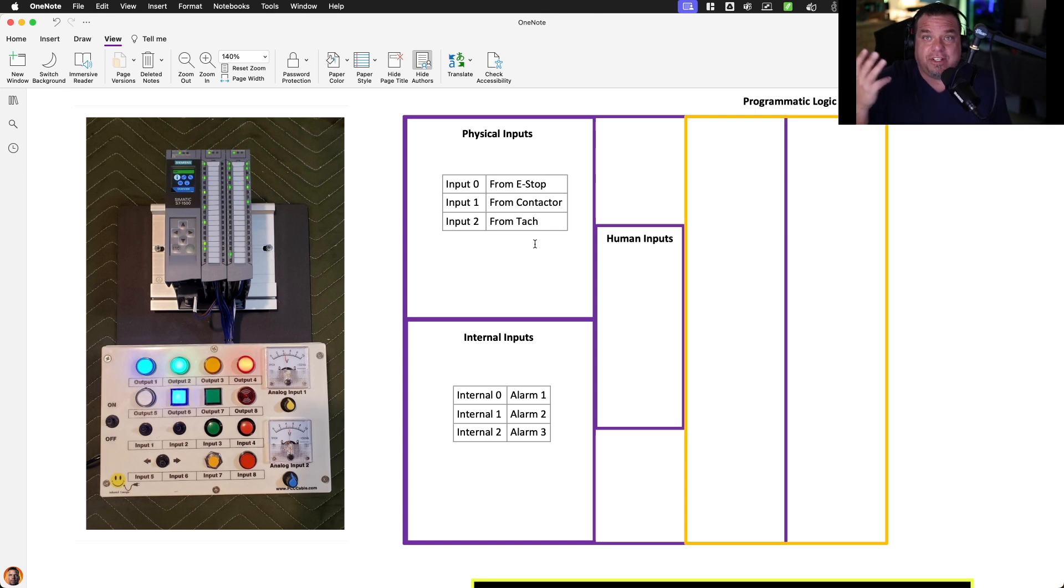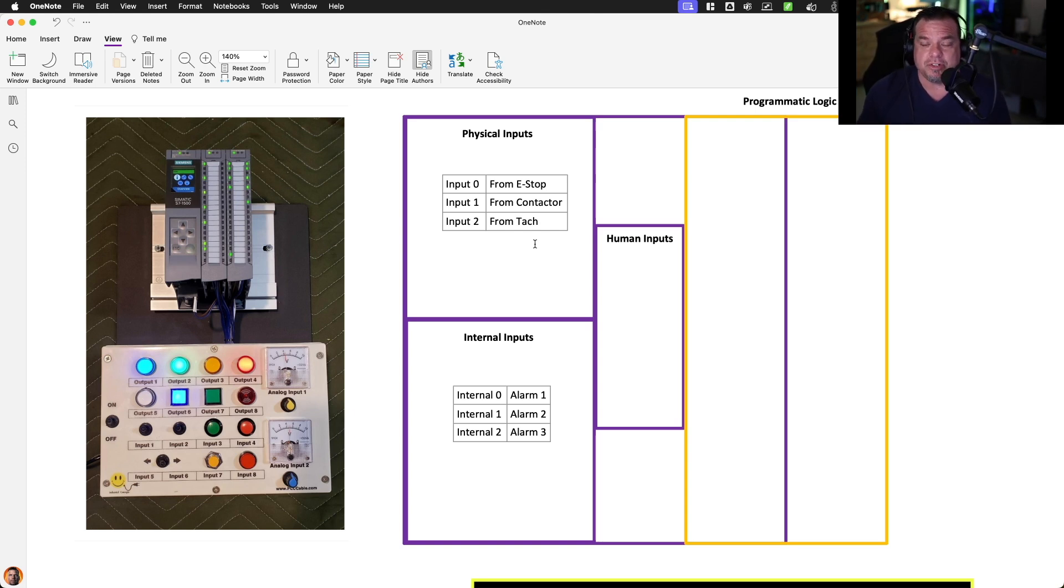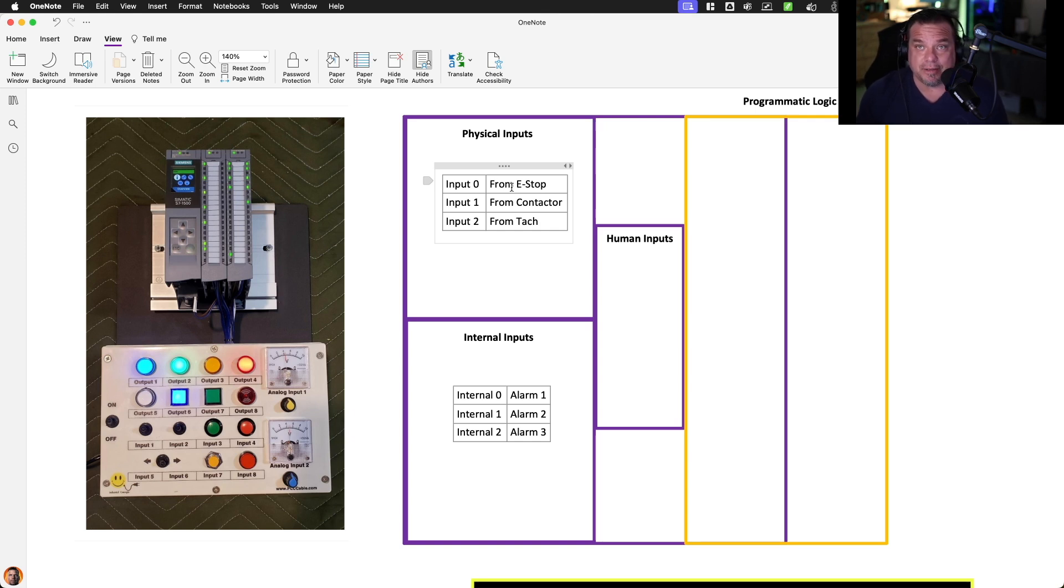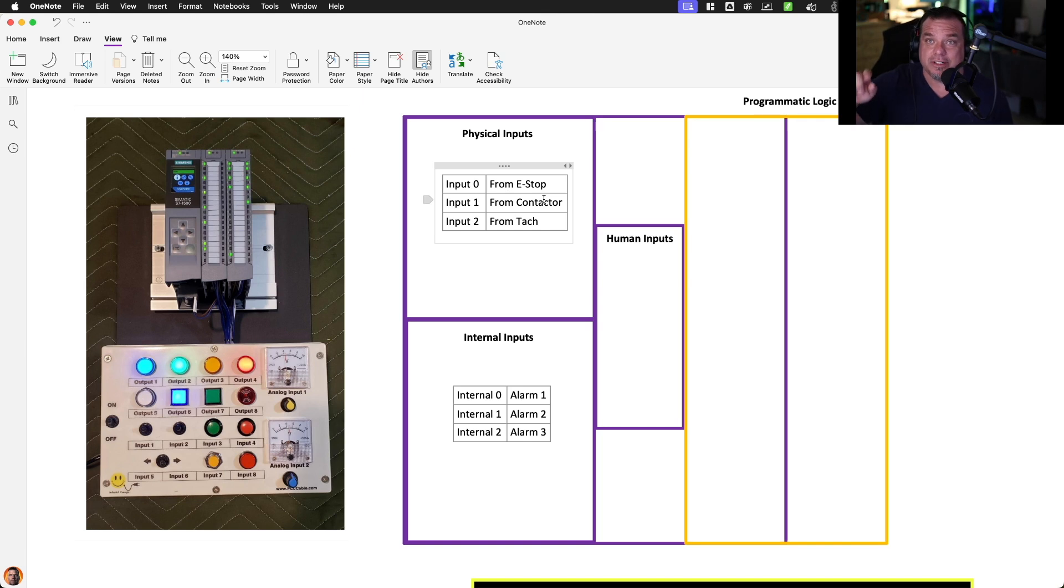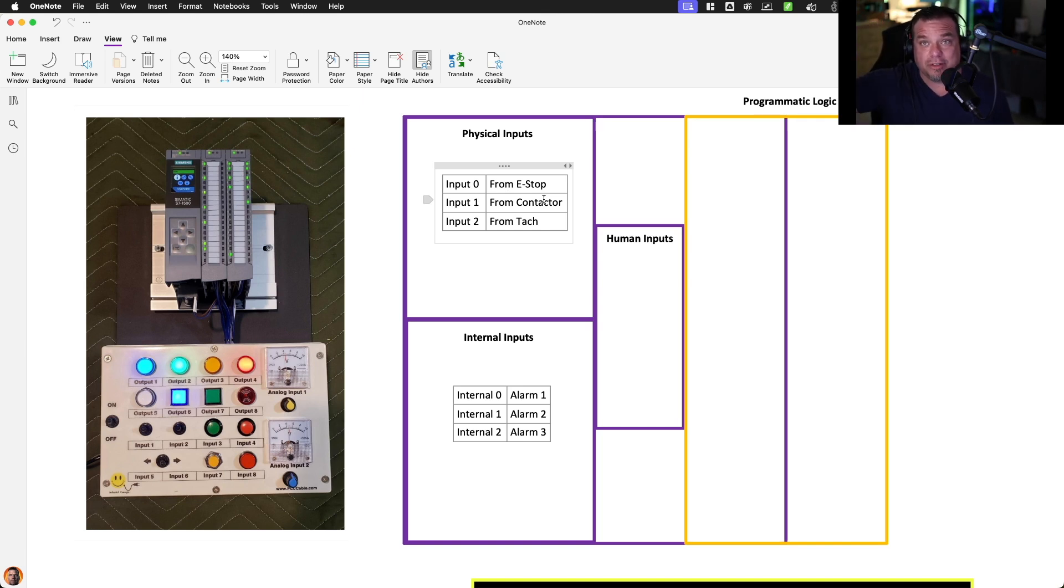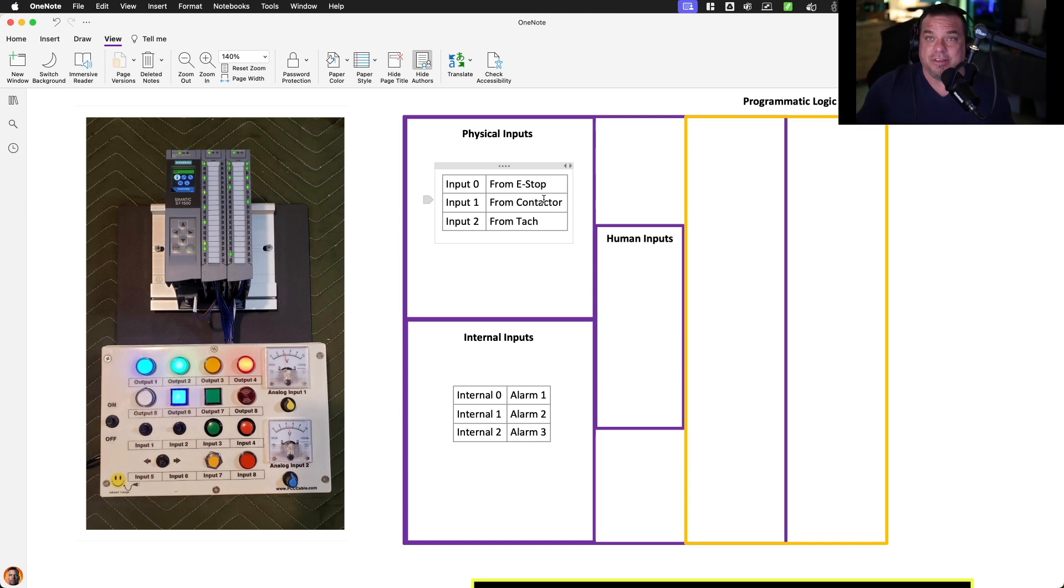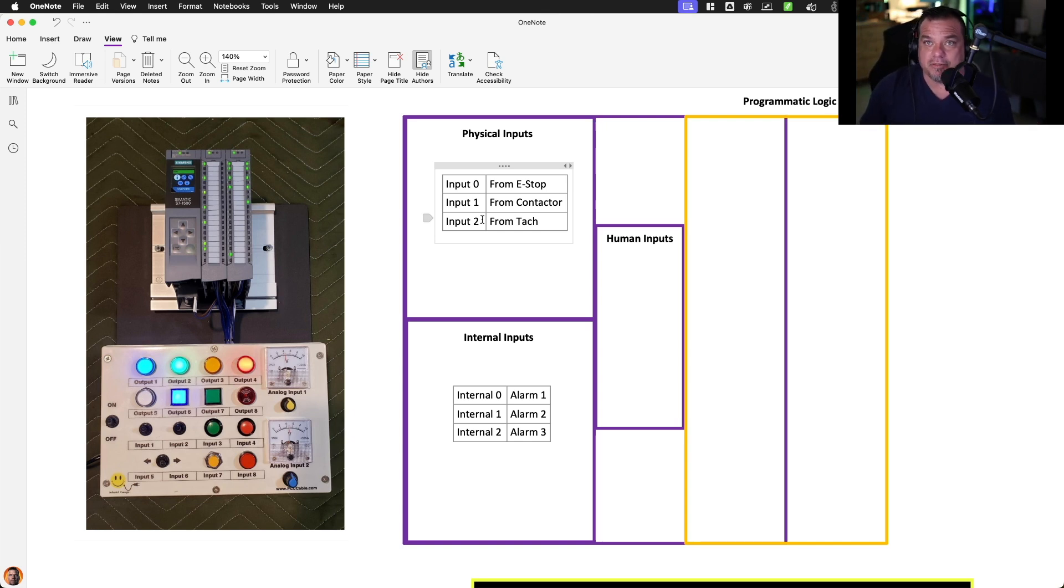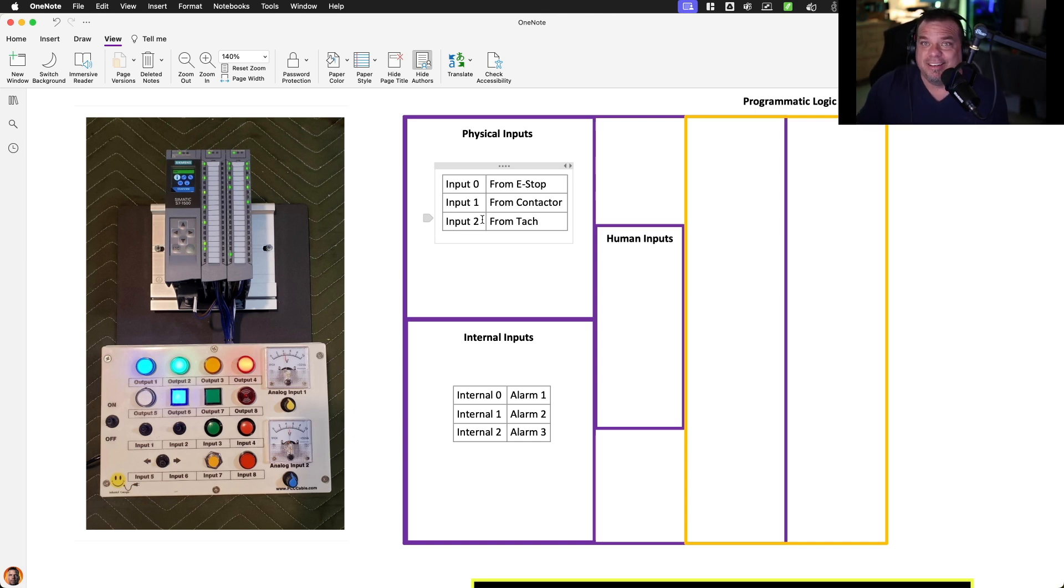In this case, three examples of physical inputs that come from the field that we might use in tracking state. We might have a physical input zero that's from our e-stop. We might have a physical input one that's from our contactor that is a motor contactor. I push the start button, the motor starts, physical contactor closes, and we get an auxiliary contact coming back telling us that the contactor is closed and we're actually moving. Input two might come from a tach. It may be an analog value that's measuring the speed on a conveyor, for example, telling us the state as we're running.